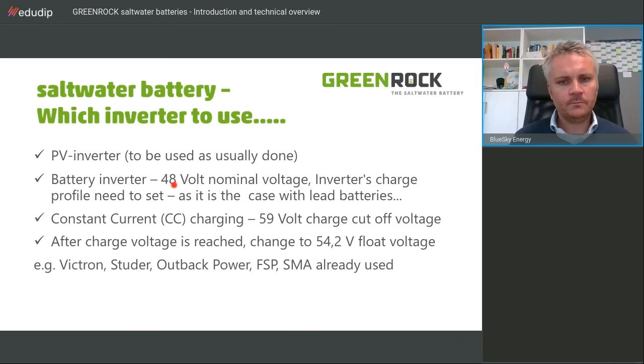So the charging is a constant current charging, and we are charging up to 59 volt charge, and then we cut it off and we change then into the float. And Studer is even mentioned here, Outback Power. Those are just examples of inverters which we have been working with, but of course there are many more battery inverters out there. Our main criterion is really that the battery inverter is on a 48 volt level and can handle that.